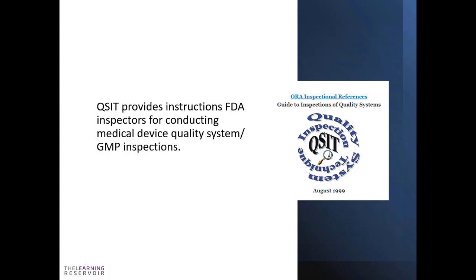QSIT provides instructions to FDA inspectors for conducting medical device quality system GMP — good manufacturing practices — inspections. It's basically a guidebook, an inspection guidebook, that FDA inspectors can use when they are conducting GMP QSR audits of medical device facilities, or as they call them, inspections.